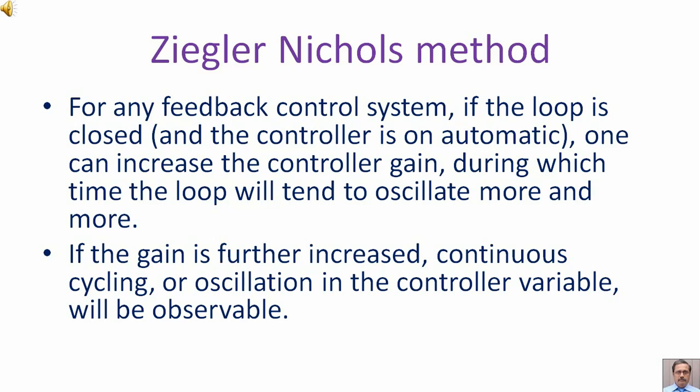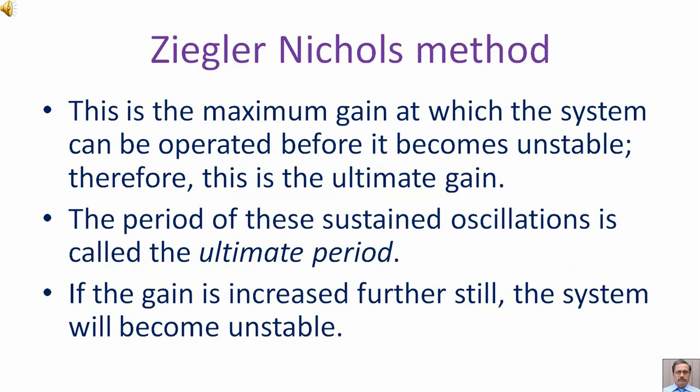If the gain is further increased, continuous cycling or oscillation in the controller variable will be observable. This is the maximum gain at which the system can be operated before it becomes unstable; therefore, this is the ultimate gain.